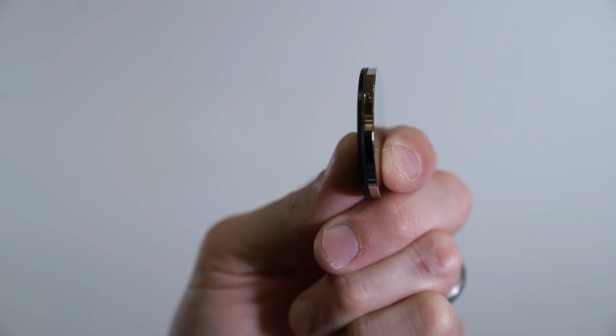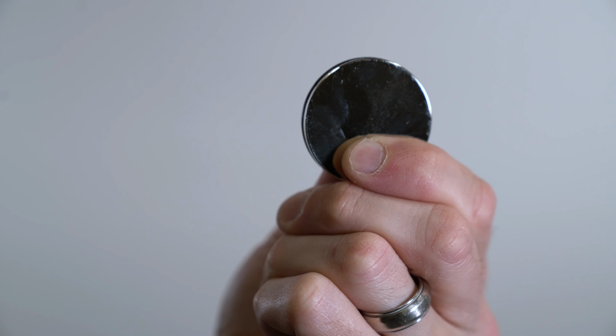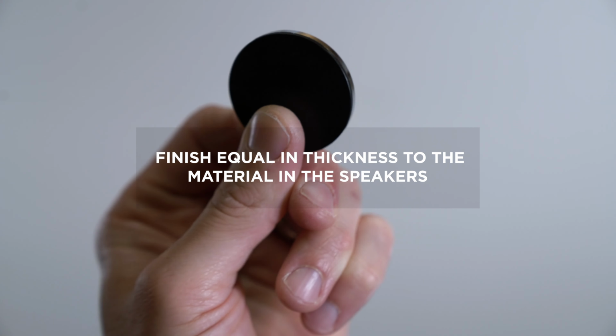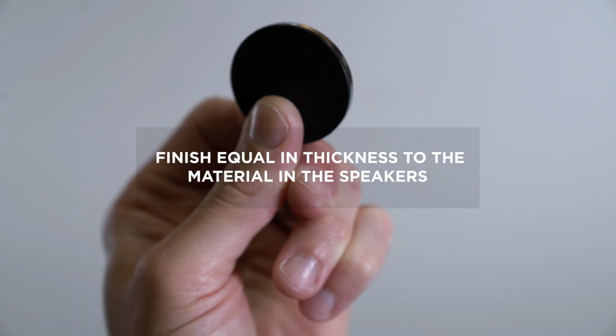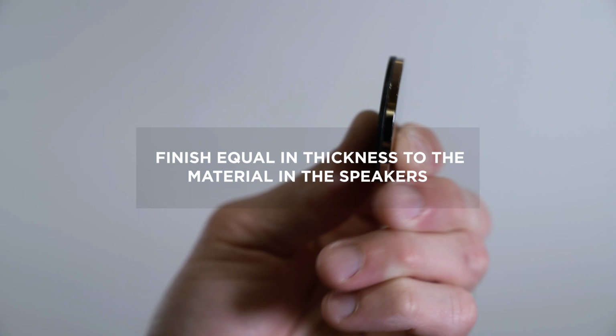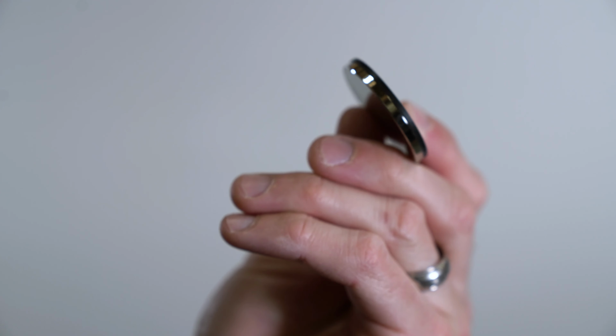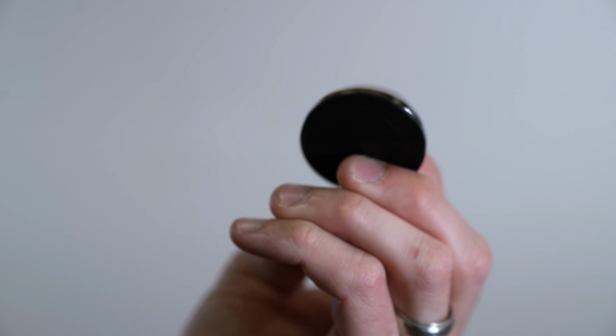Before you begin, locate the included calibration disc. This steel disc is covered on one side with a finish equal in thickness to the material that covers the discs that are embedded in the face of the invisible speakers. This disc will be used to zero out the gauge.